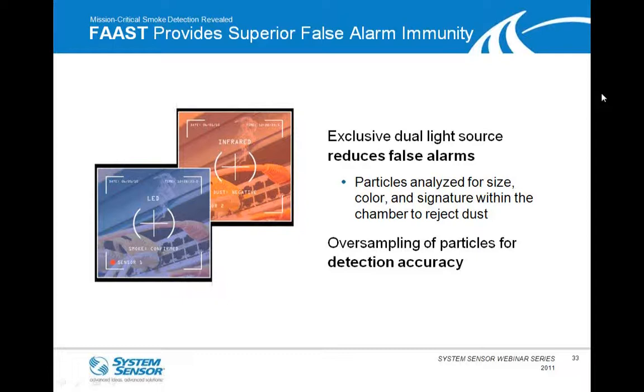Smoke particles and dust particles have a drastically different signature, and with this 2-source capability and the algorithms that are interpreting that data coming in from the 2 sources, we get much improved false alarm immunity with the FAAST device. And then again, we take oversampling of those particles. So even once we've gone through all that analysis, we look at multiple samples, we delay it a little bit just to make sure we actually have a fire condition. And when I say delay, we're talking milliseconds type timing.